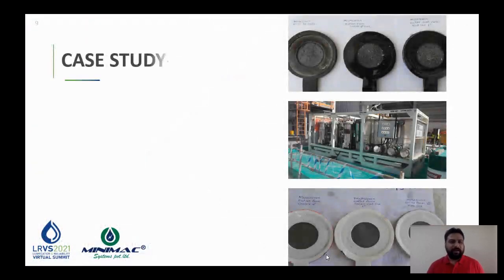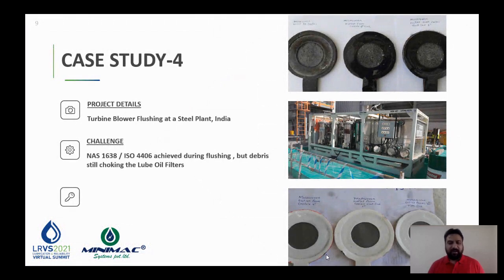The next case is from a steel plant in India, where I belong. There was turbine blower flushing being carried out, and the client or EPC company concluded the flushing by checking the NAS 1638 results and the ISO 4406 results. Even after checking these results and concluding based on these parameters, they started the turbine blower, and the day they started it, it tripped due to heavy debris found on the duplex filters of the lube oil system.